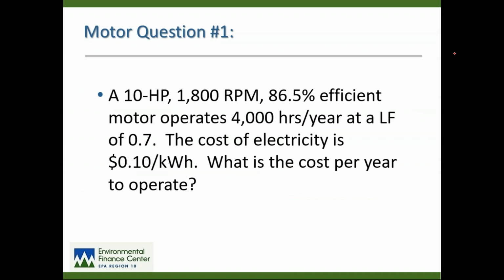So here's a typical question. And again, a lot of numbers here, don't try to memorize them all, but I wanted to get you familiar with the concept. Let's say you have a 10 horsepower motor. It's 86.5% efficient, and you'll get that information off the nameplate. This motor is running 4,000 hours a year, and it's loaded at 70% of its rated horsepower. And your cost of electricity is 10 cents a kilowatt hour. And I'll tell you, a lot of people in California would be happy to get 10 cents a kilowatt hour. In many cases, it's 2 and 3 times that.